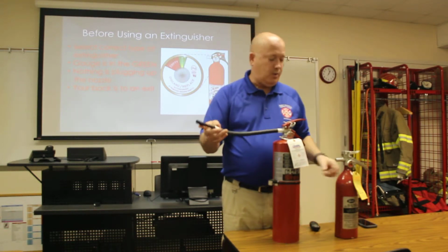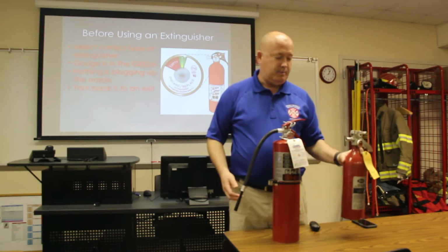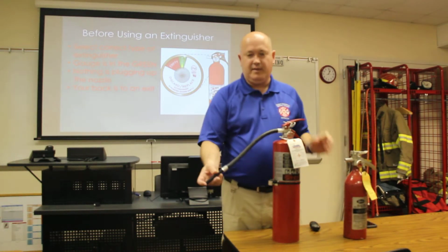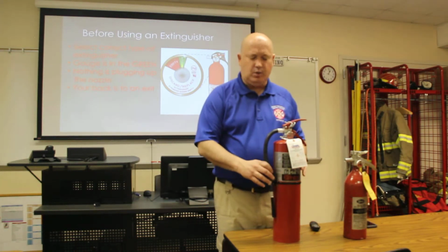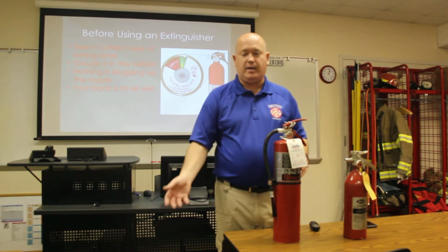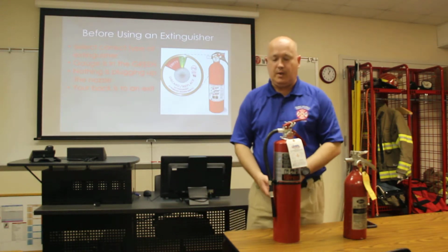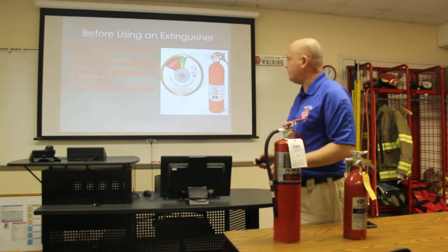Also, with a hose or with a nozzle, make sure someone hasn't stuck things like bubble gum, surprise, surprise, in the school system, up the end of a nozzle, or a broken pencil, eraser. We found all kinds of things in a school setting that have been lodged in that. If something is lodged in that, it's not going to work for you. So choose a different extinguisher and make sure that ultimately gets pulled out of service until it's fixed.